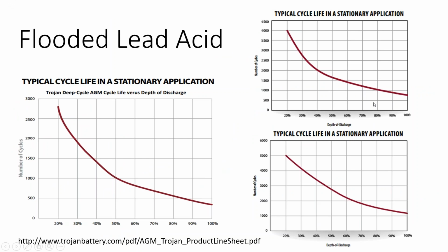And so you can have a lead acid battery that says, oh, you should only cycle this down no more than 35%, because then you get into the bulk phase. Well, here's a different lead acid battery that you can cycle it down almost to 60% before you get into the bulk phase. And here's a different lead acid battery where you can cycle it down to about 50% before you get into the bulk phase.